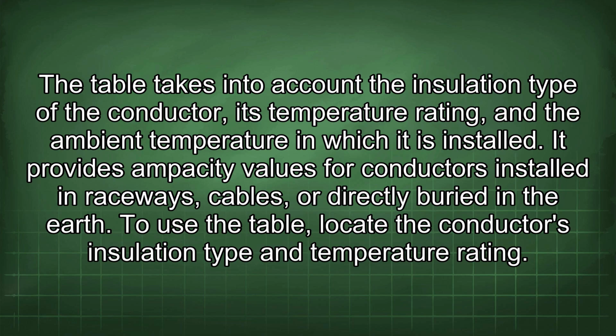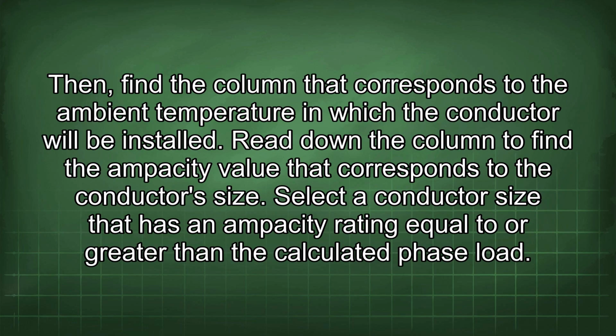It provides ampacity values for conductors installed in raceways, cables, or directly buried in the earth. To use the table, locate the conductor's insulation type and temperature rating. Then, find the column that corresponds to the ambient temperature in which the conductor will be installed. Read down the column to find the ampacity value that corresponds to the conductor's size. Select the conductor size that has an ampacity rating equal to or greater than the calculated phase load.